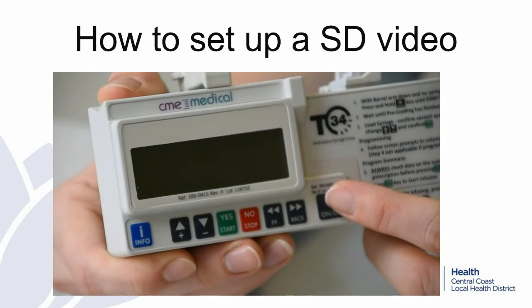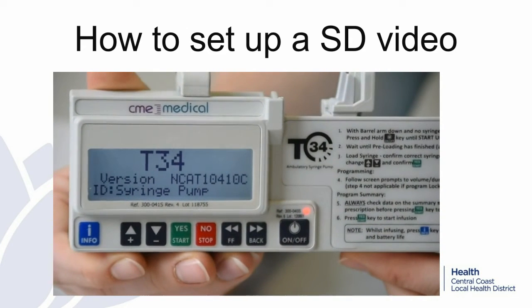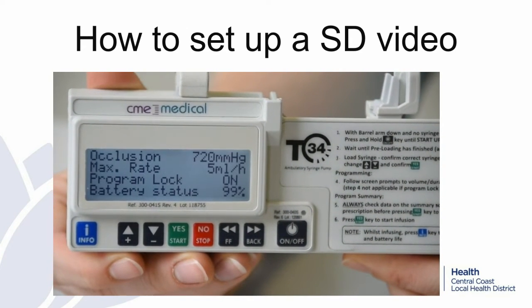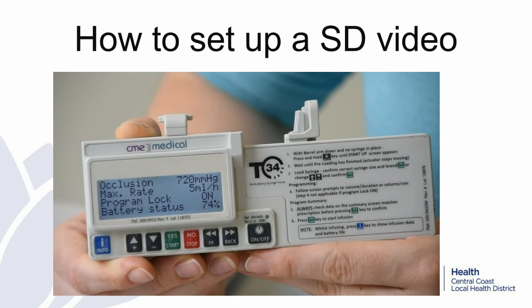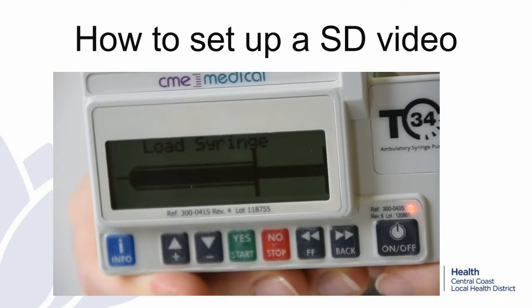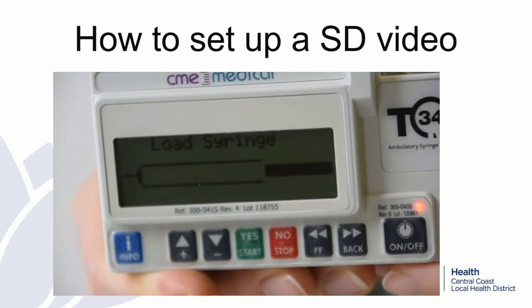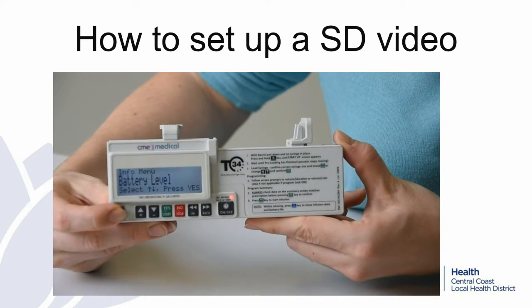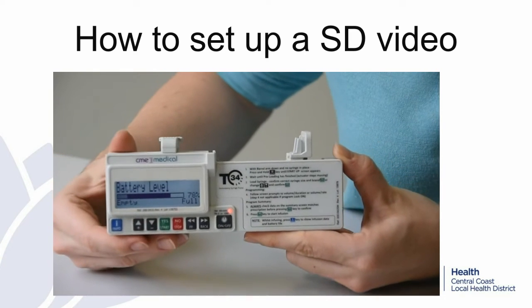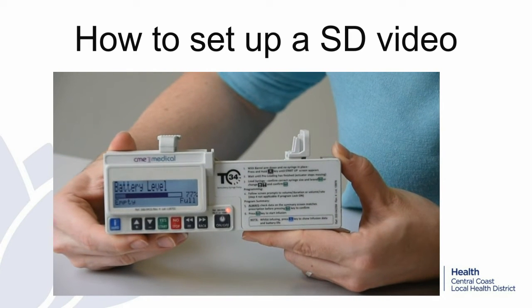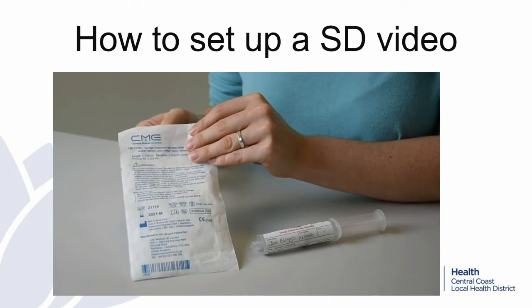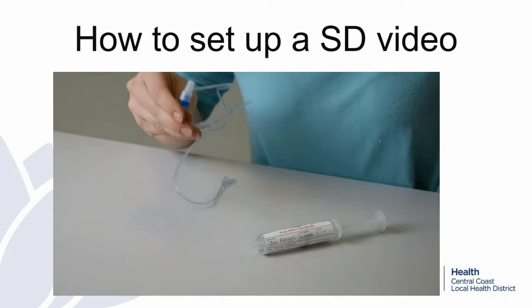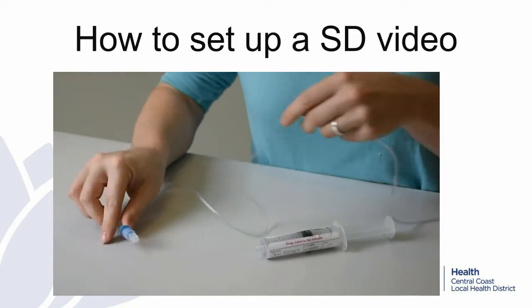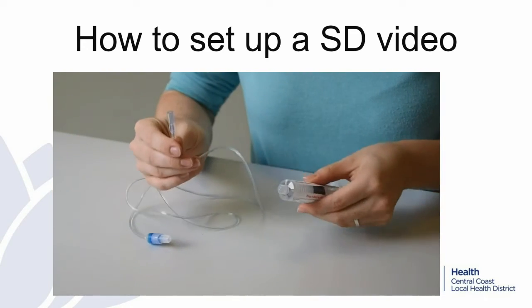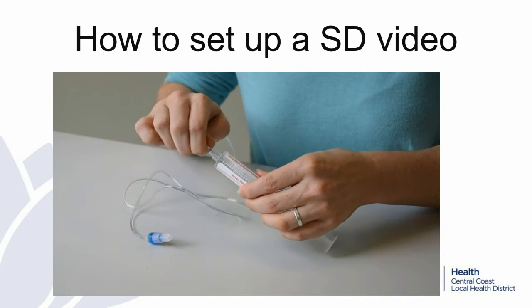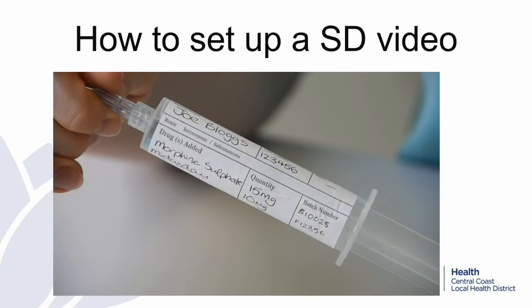Turn on the syringe pump. Keep fingers out of the way as the pump does its preloading checks once the machine is turned on. Preloading. Once the screen says load syringe, check the battery level by pressing info and then yes. Ensure there is enough for 24 hours, which is 35% and above. Next stage is to prime the line if it is a new syringe or new prescription. You must ensure you are using a CME line. Once you have labelled your syringe and primed the line, you are ready to set up the syringe pump.